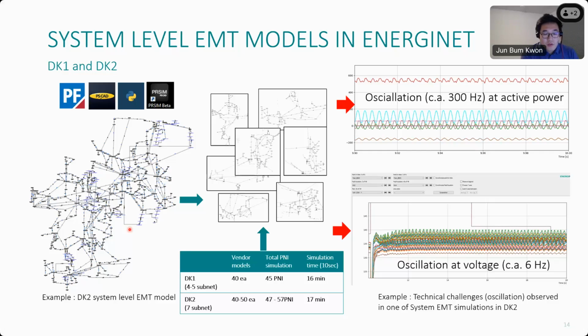Some examples that we have observed, which were not observed in RMS system level studies, are basically more interaction and oscillation issues. For example, some oscillations in active power around 300 Hertz, and around 6 Hertz in voltages, depending on the scenario, configuration, and load flow scenario. We could observe such oscillations coming from interactions between the power electronics devices, and interaction between the power electronics and the grid. Handling and observing such oscillations was quite different compared to RMS-based studies.